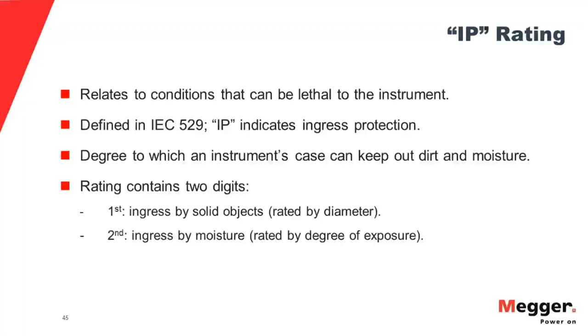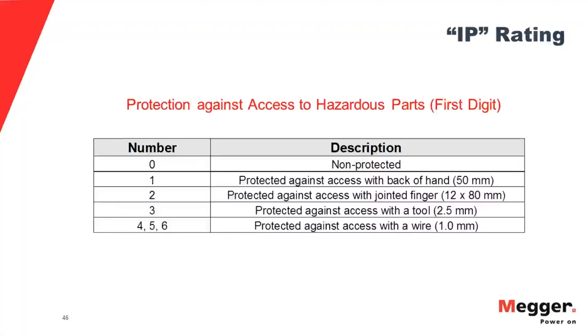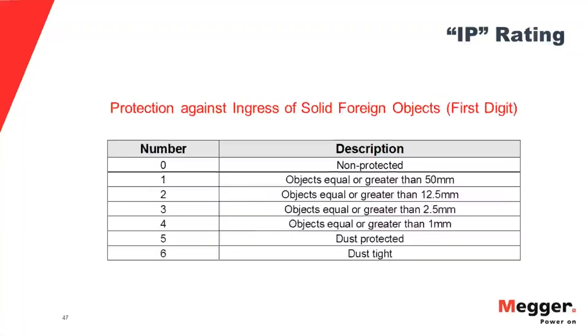In the old days, especially in the mining industry, we would get instruments back for repair, and they would be packed with powder from stone being mined and so forth, or coal dust or something like that, and that would be all over the PC board, and that's the end of the functioning of the unit. So look at your ingress protection. These are a quick look at some of the numbers and what they mean, and just make sure that you match your IP rating to the environment in which you're going to be using your piece of equipment.